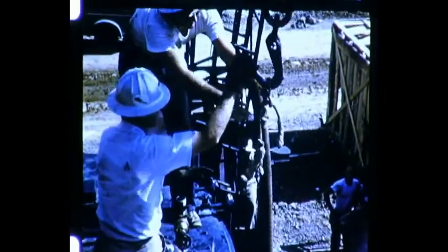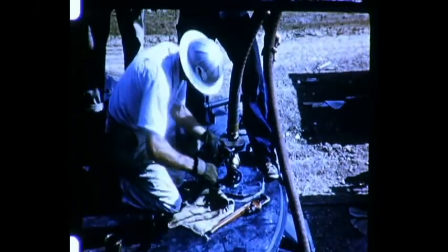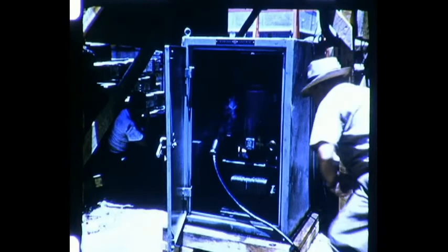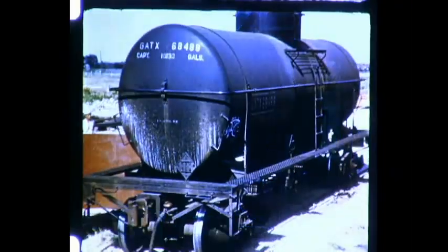Oil filling of the transformer is done under vacuum to keep the insulation free of air and moisture. This vacuum pump will exhaust the carbon dioxide shipping gas and remove air from the oil as it sprays into the tank from the top. A pipe-threaded opening in the cover accommodates a valve for the vacuum line. And with the valve in place, the vacuum hose is hoisted to the top of the transformer and connected. Then, after the cooler valves have been opened, the vacuum pump is operated for 4 hours prior to filling, during filling, and for 4 hours after filling.